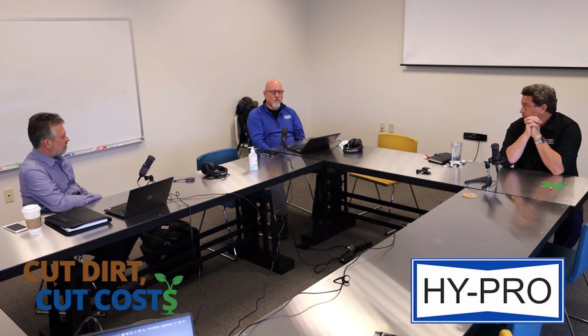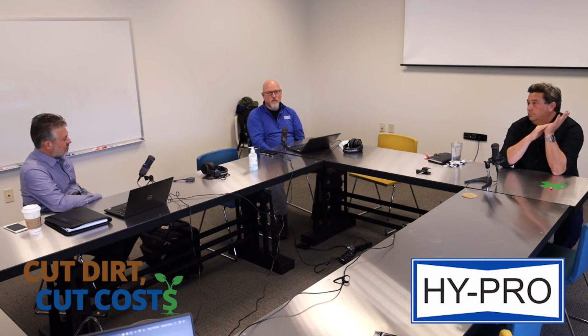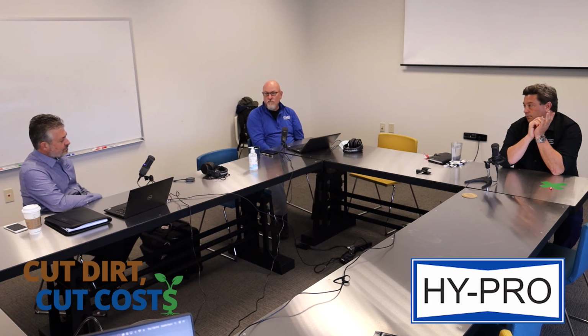Depth media is real efficient in removing insolubles, but because of the chemical process of adsorption, it can also remove at least a small amount of soluble or dissolved oxidation byproducts. And then the final stage is ion charge bonding resin. That technology actually focuses on the oxidation byproducts that are in solution or those that are dissolved. And with that technology, we can run much lower MPC values than any other technology. But which technology we apply is dependent on the lubricant itself that we're trying to mitigate.